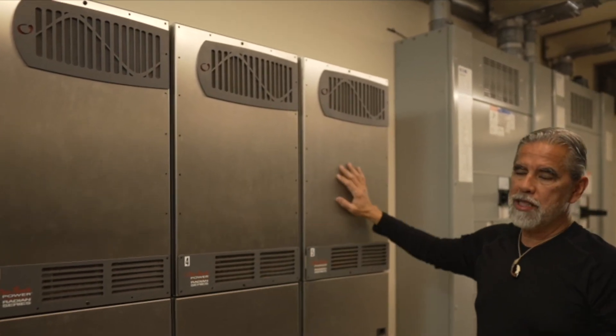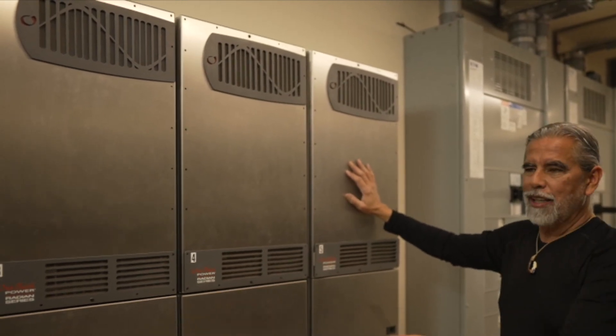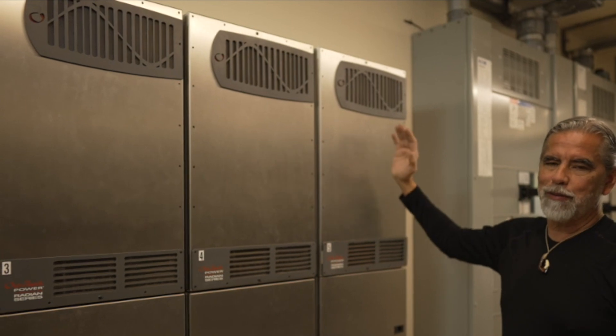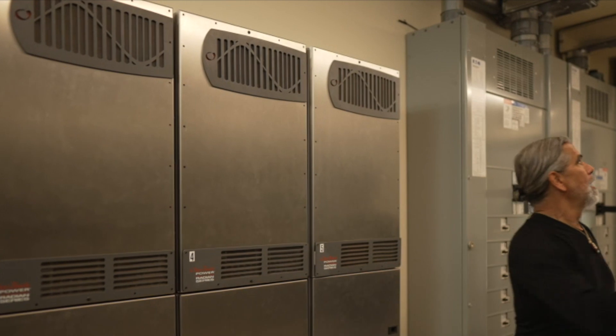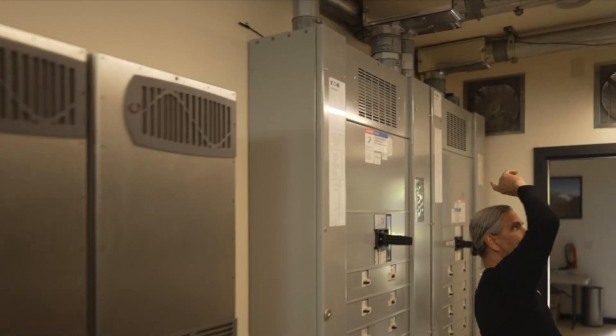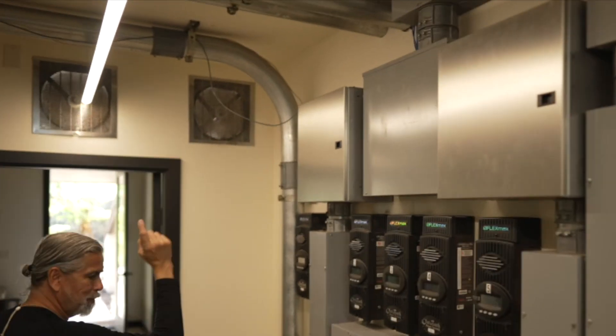So we have five of them for 40 kilowatts at any given time. The reason we have five small ones instead of one big one is they break down from time to time, so the worst it gets is we go from 40 down to 32 kilowatts. Whatever extra power we have goes to the battery through these conduits — so follow me to the batteries.